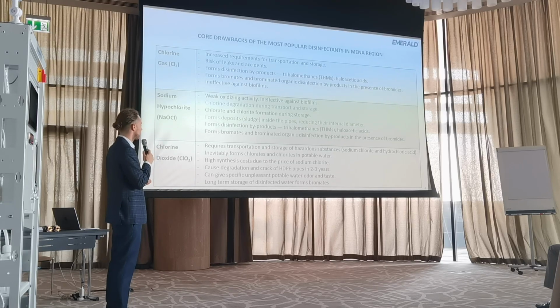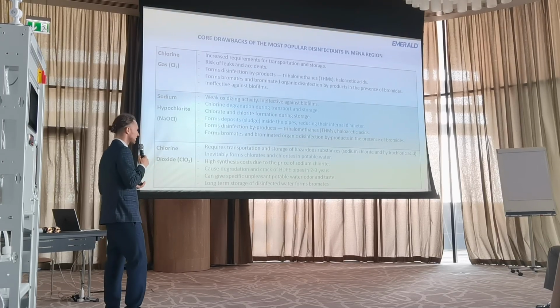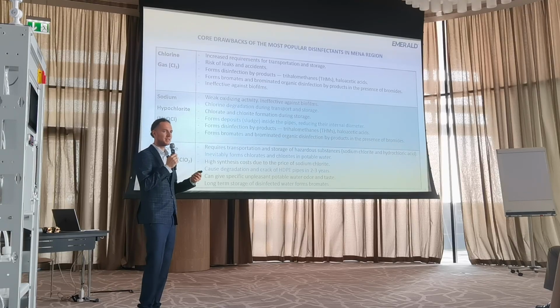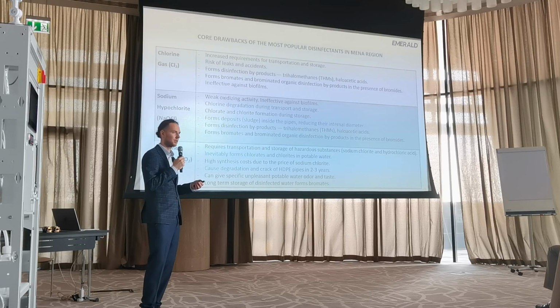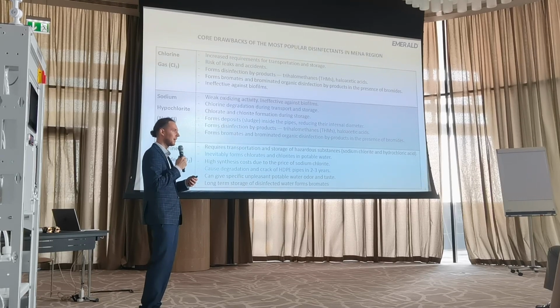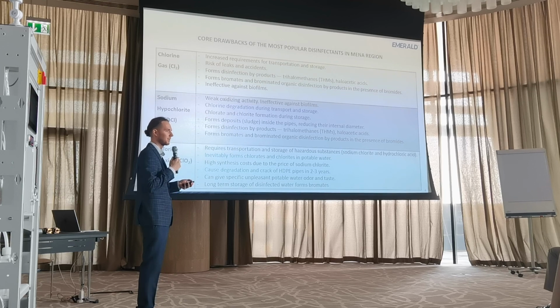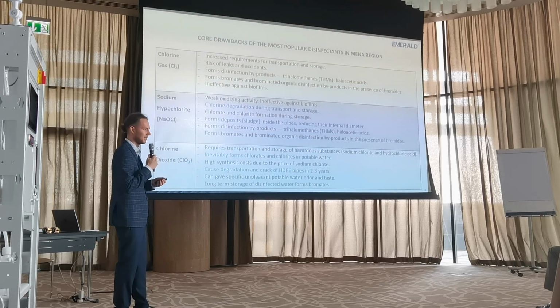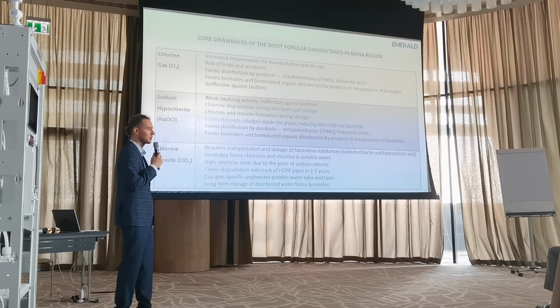One of the new problems now being investigated, which I've heard about from several operators, is that using chlorine dioxide for potable water has increased the speed at which HDPE pipes crack and get damaged. This is still under investigation, but the people I've been speaking with have concluded that it's because of chlorine dioxide.